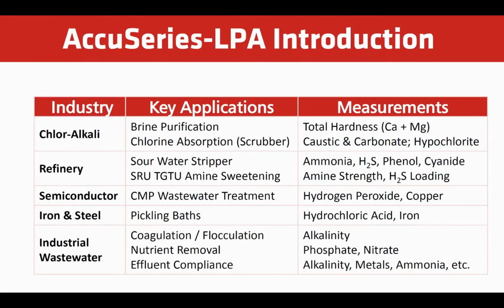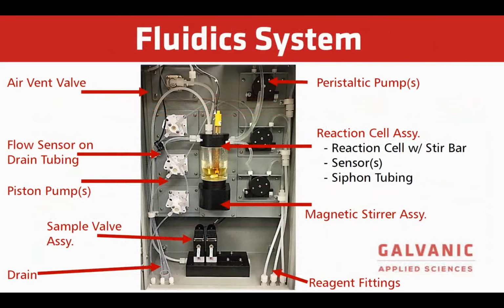or ammonia, etc. Here we're going to take a look at the lower enclosure where the fluidics are. The reaction cell, this is where we actually add the reagents through these various piston pumps or peristaltic pumps. It does the reaction. In this case, it looks like it's a pH probe, so a potentiometric titrator. The sample comes in the bottom through the sample valves, and those are energized in time when it's ready to take a sample and fills the cell.